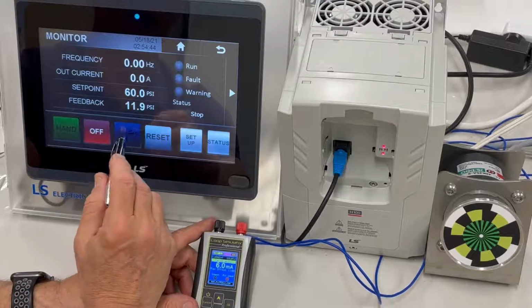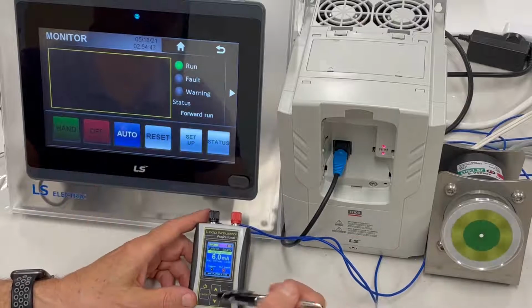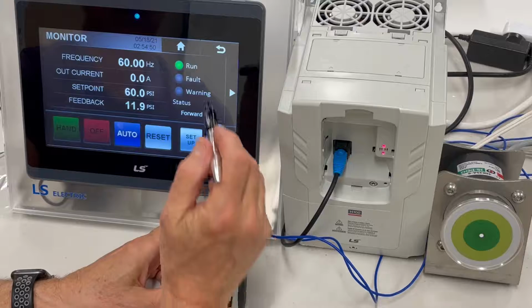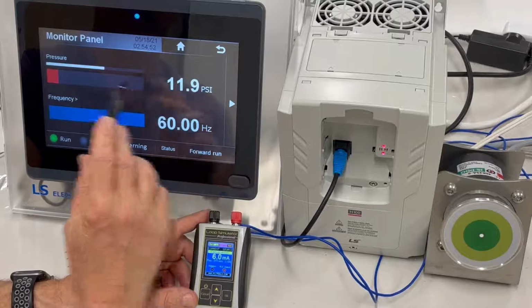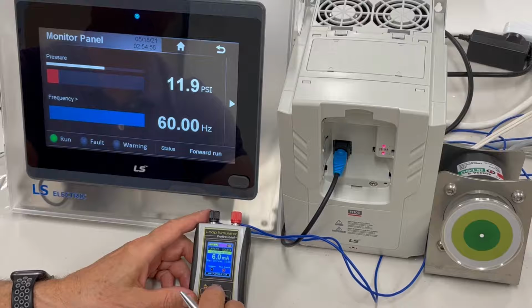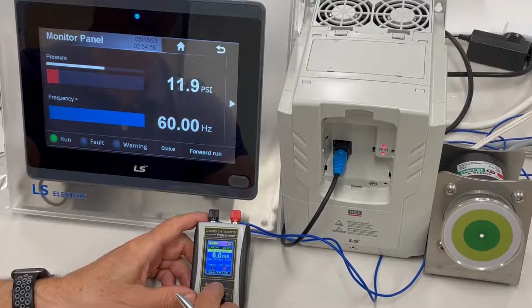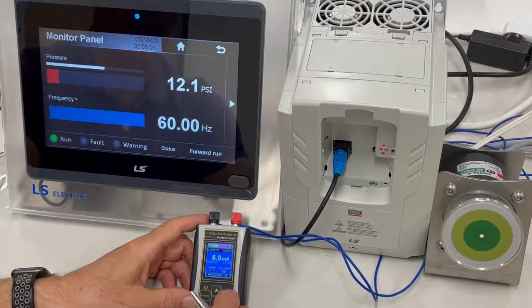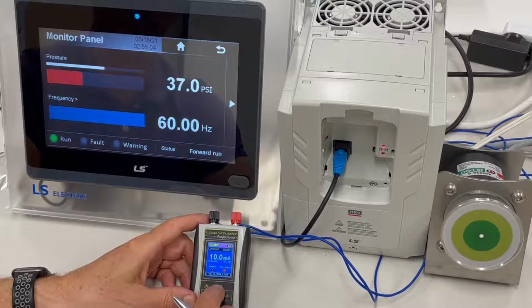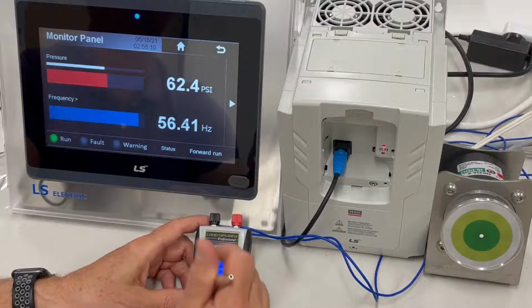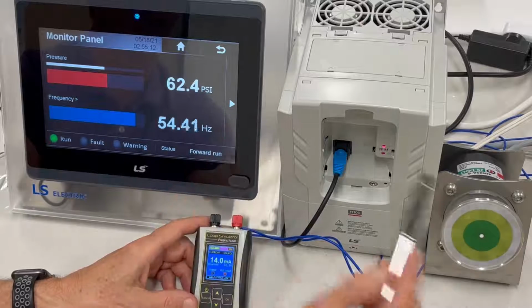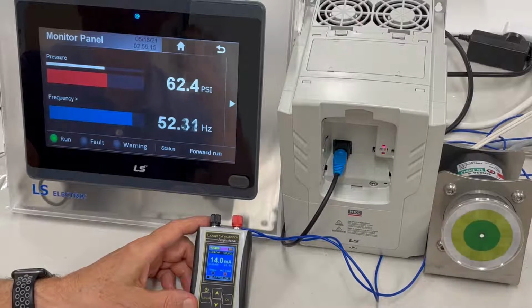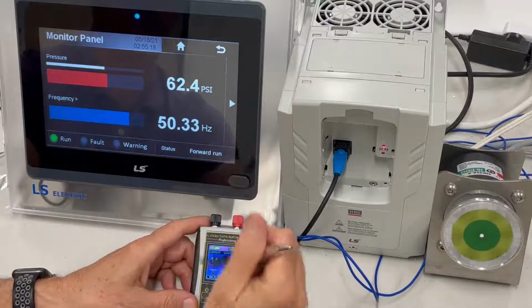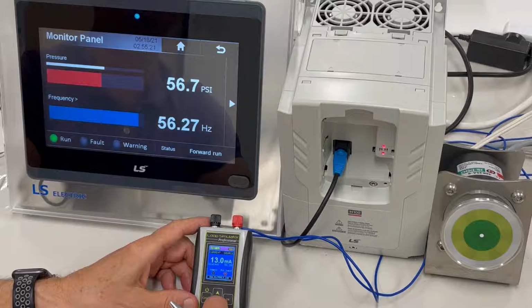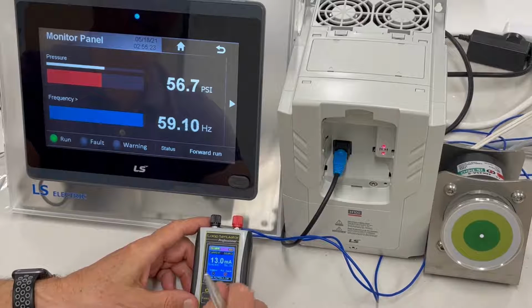So here we are. We're going to get this started by hitting the auto mode twice. So we're at 6 milliamps, which basically is 11 PSI. Here's our set point over here. So as we ramp this up, I just forgot to hit the calibration key there. So we ramp this up. We're going to get close to the set point, and now we've hit over 60 PSI. We're at 62. So now you notice that the motor is going to a sleep mode, and it will slowly ramp down. But let's say the pressure drops down again. It will go right back seamlessly.